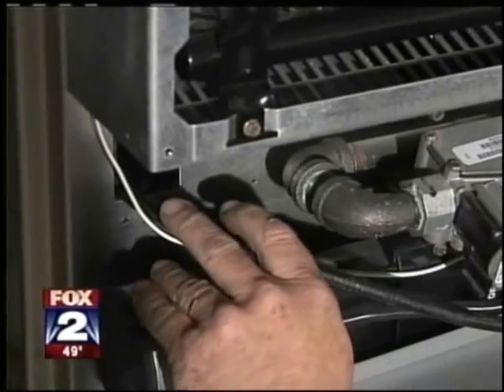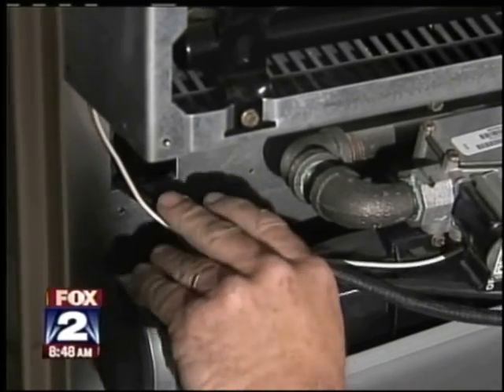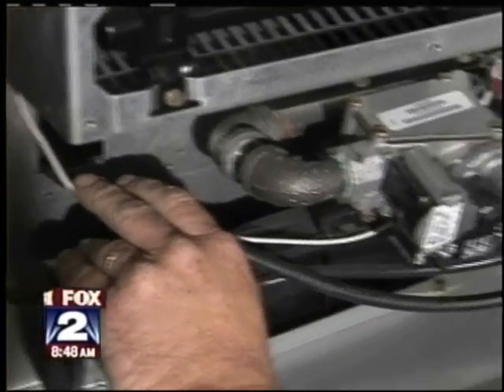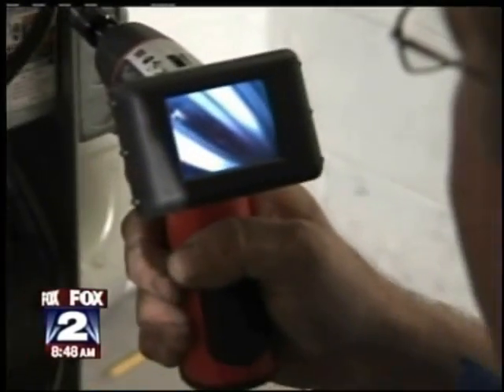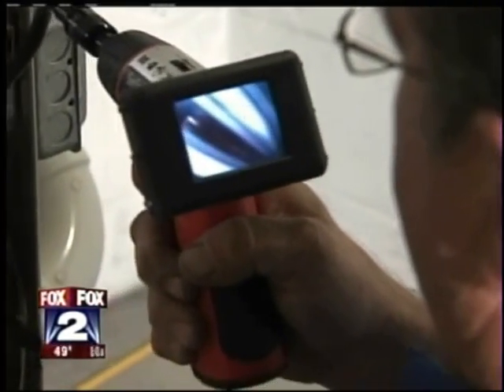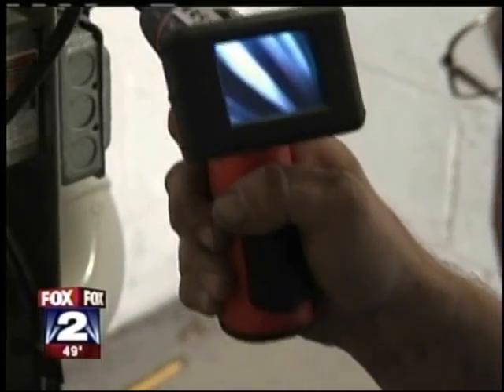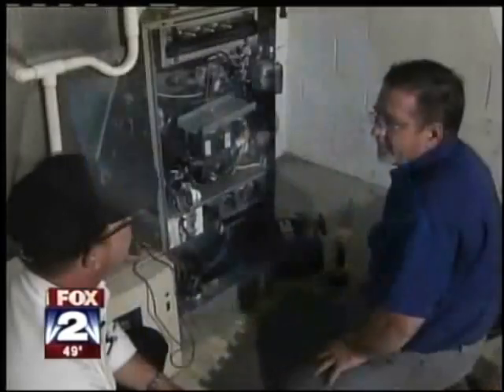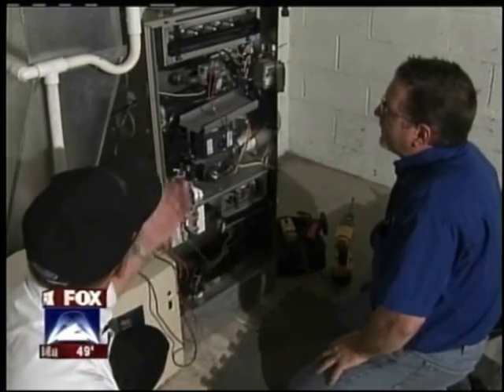Steve, our technician, can you tell me a couple of things you're doing to recondition this old furnace? One of the things we're doing is inspecting the heat exchanger, looking for any breaches or cracks, which are safety issues. Cracks in the heat exchanger can lead to carbon monoxide poisoning, correct? That's correct — potentially life-threatening.